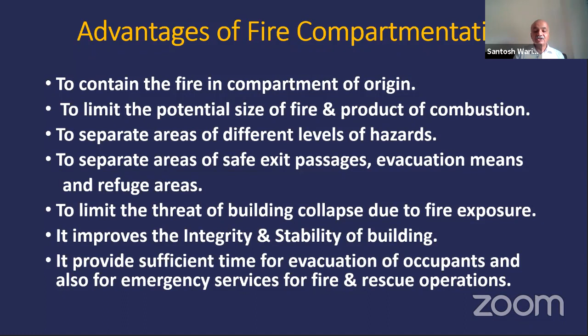Then it limits building collapse. When a building is exposed to fire, it should remain standing for a greater time, so that all evacuation, firefighting and rescue operations can be done without any problem. That can be achieved with this compartmentation. It improves the integrity and stability of the building, which we have already discussed, so it will remain intact for longer, providing sufficient time for evacuation and for the firefighters to reach the upper floors to carry out firefighting and rescue operations.